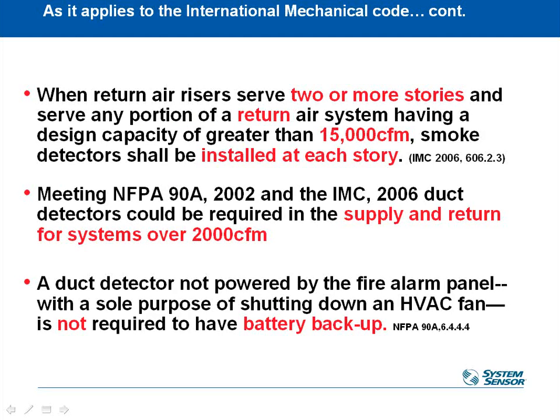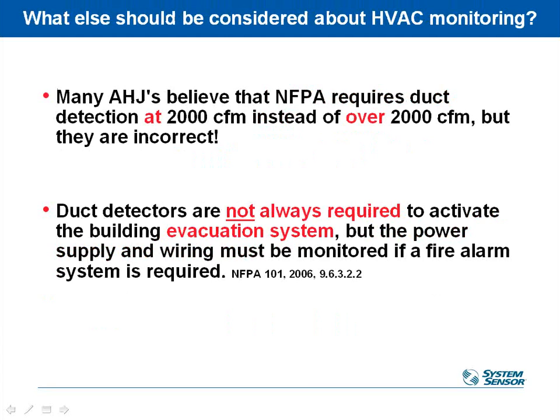Additionally, if the duct detector is not powered by the fire alarm panel, which on smaller systems it typically is not, and his only job in life is to shut down the HVAC fan, and once again on smaller systems that's typically all he has to do, then you're not required to have a battery backup. That comes up every once in a while.